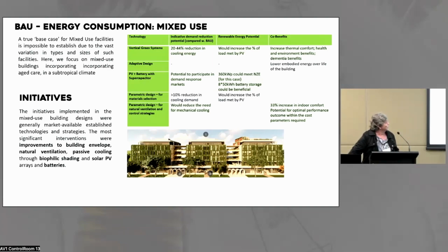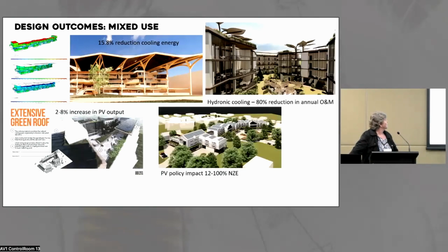Another important thing this design studio looked at was the value of parametric design, where you can explore the optimal building material characteristics to give the lowest kilowatt cooling per square metre, testing different glazing ratios, insulation ratios, etc. A lot of design teams in industry don't actually use the power of parametric modelling to determine the best insulation, glazing, and so on.